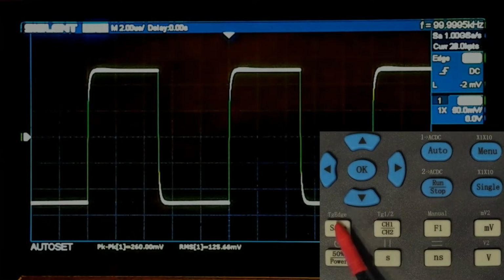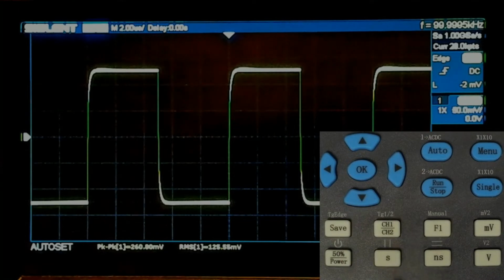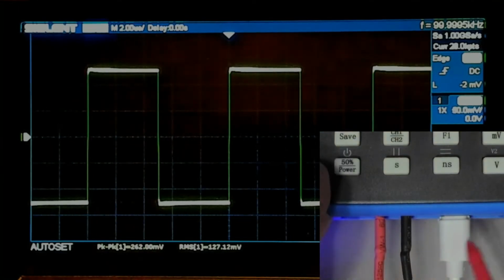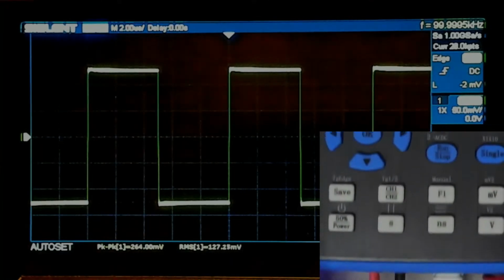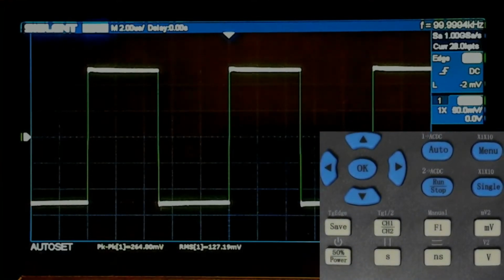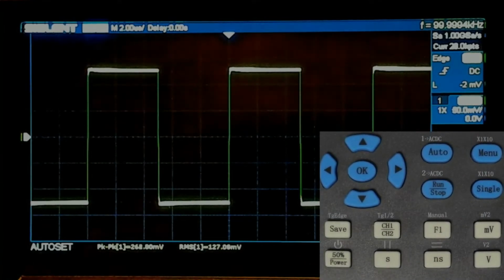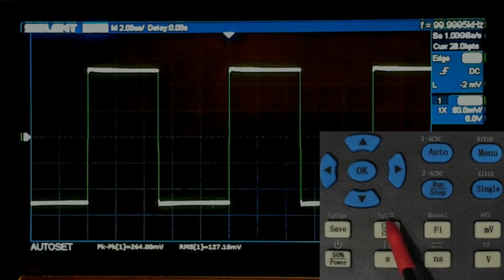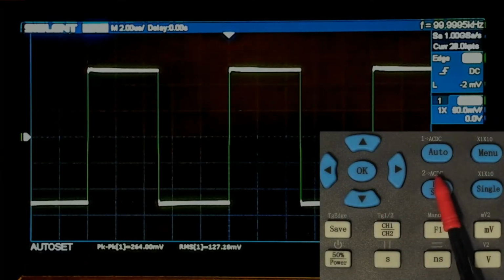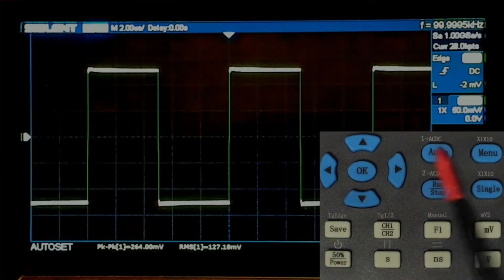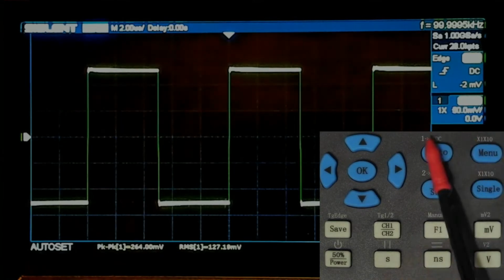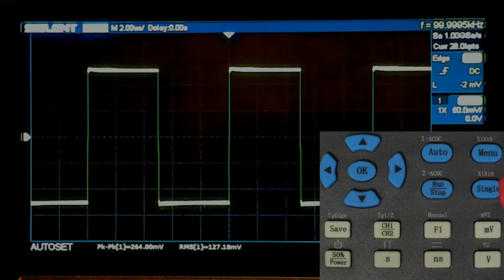And you can actually save waveforms, up to 250, I believe. And then there is a mode where you can put this thing in, where it's got a USB port here at the bottom. The USB port can be used to plug into a computer, and then it'll look like a drive, and then you can download the waveforms that you've captured. Run stop. This is for auto. When you feed a signal in there and you hit auto, it automatically centers it and selects a trigger for it.